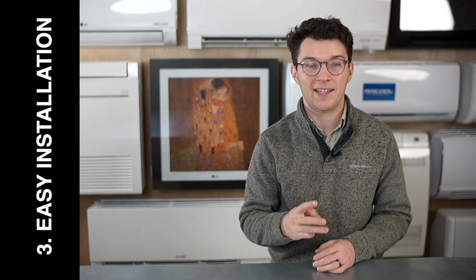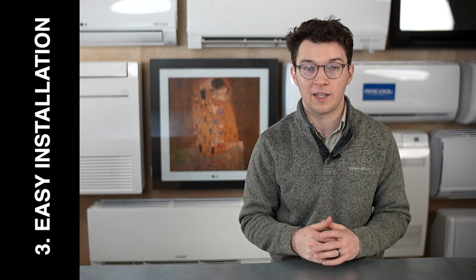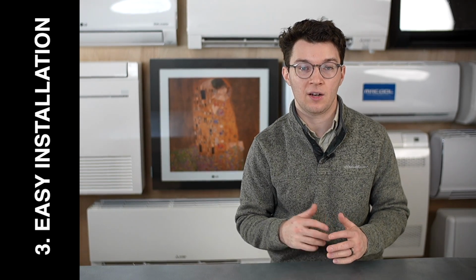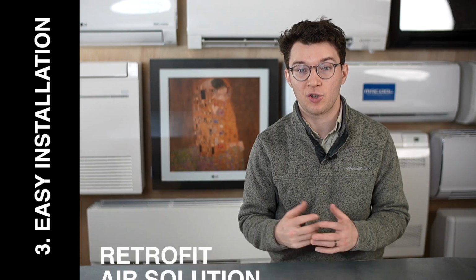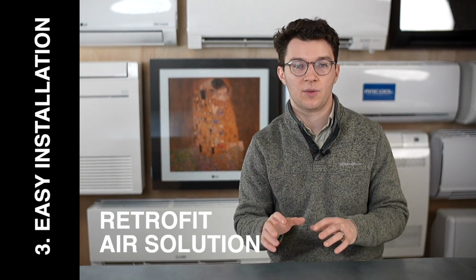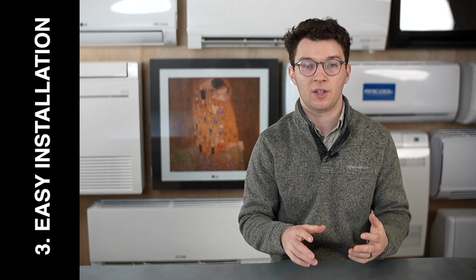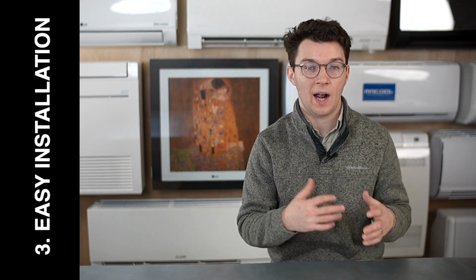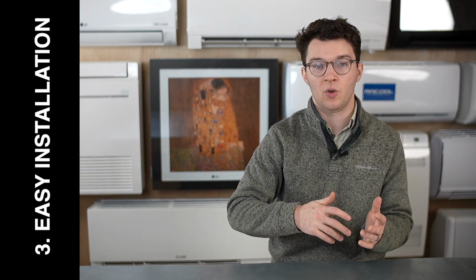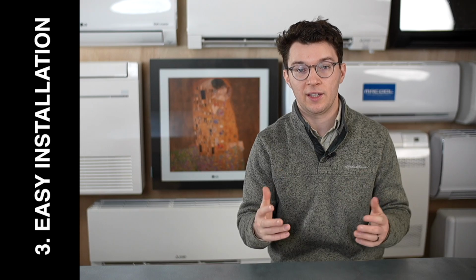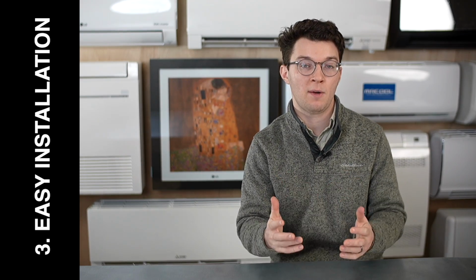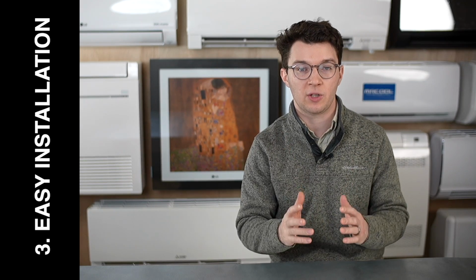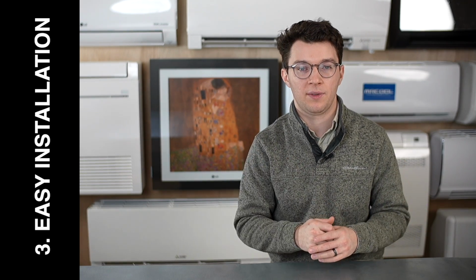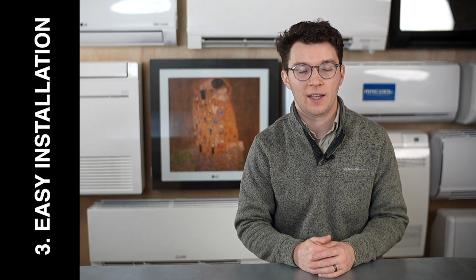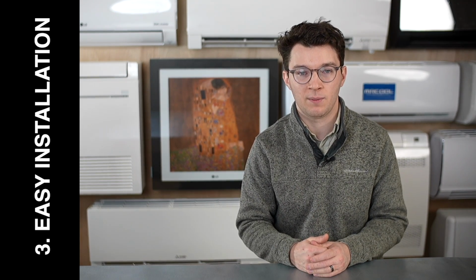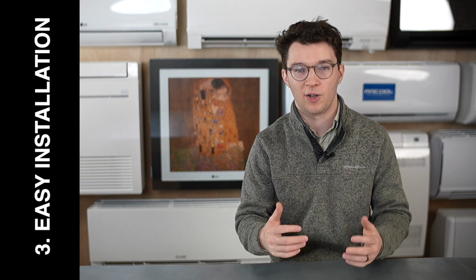The third benefit is easy installation. Mini splits aren't that difficult to install and can work for both new construction and existing houses that can be retrofitted. Since the indoor and outdoor units are connected by refrigerant lines and communication cable, those can be run either inside the wall or outside the wall. So depending on whether it's new construction or an existing home, you can really customize your installation based on your requirements. It's not like ductwork, where in most cases you're wrapping it with 2x4s and then drywalling over it. That can be a messier process, but ductless systems can be installed without a larger home renovation.